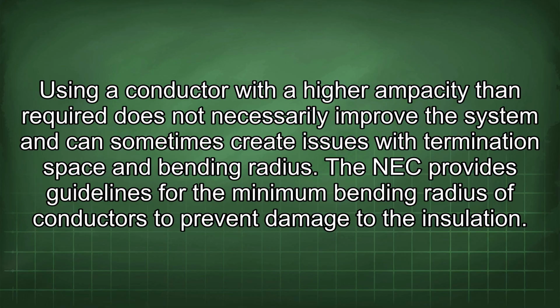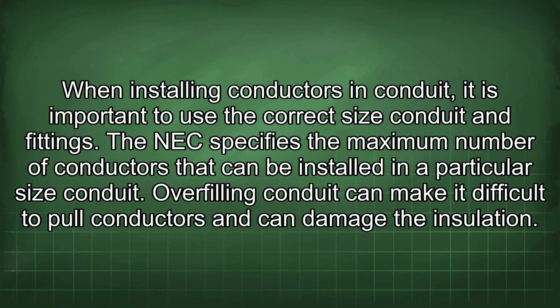The NEC provides guidelines for the minimum bending radius of conductors to prevent damage to the insulation. When installing conductors in conduit, it is important to use the correct size conduit and fittings. The NEC specifies the maximum number of conductors that can be installed in a particular size conduit. Overfilling conduit can make it difficult to pull conductors and can damage the insulation.